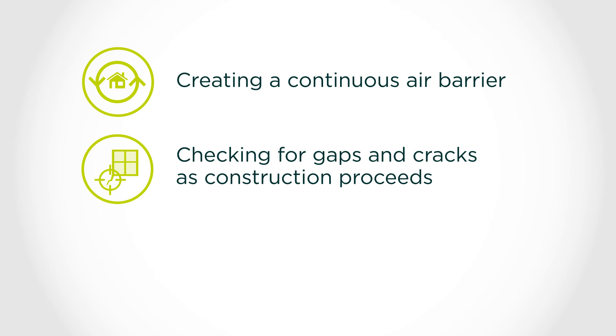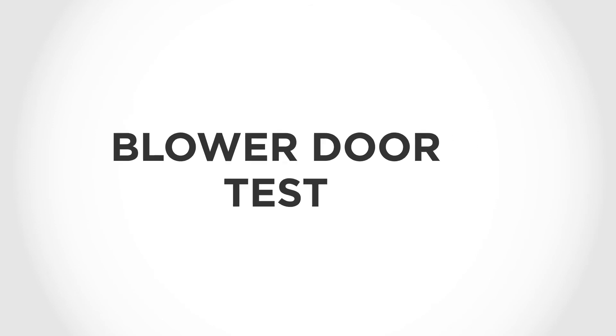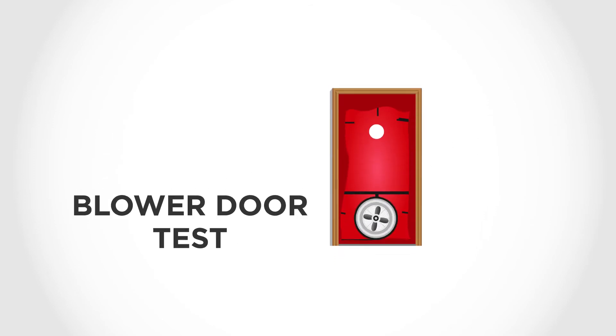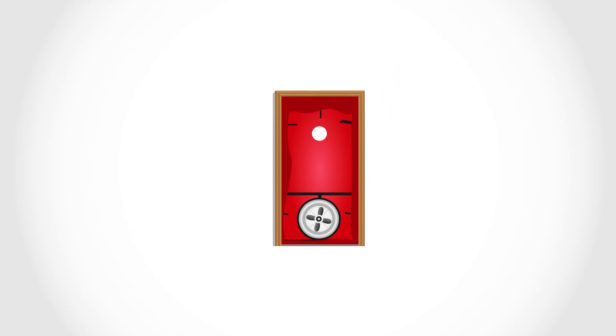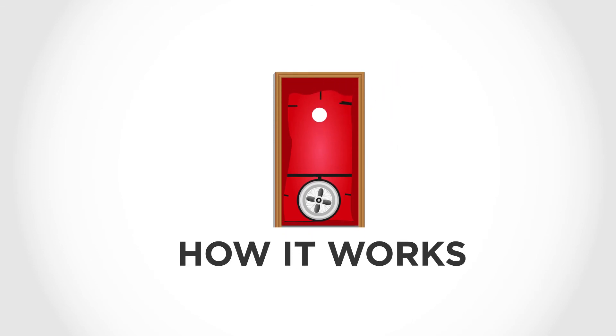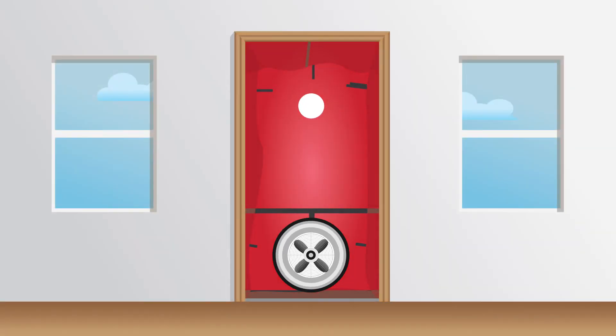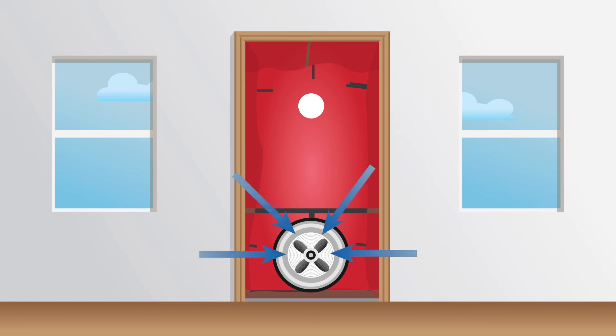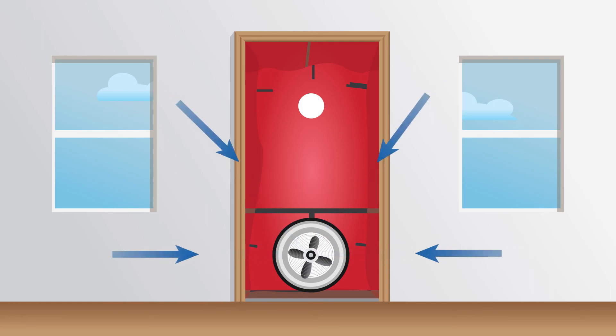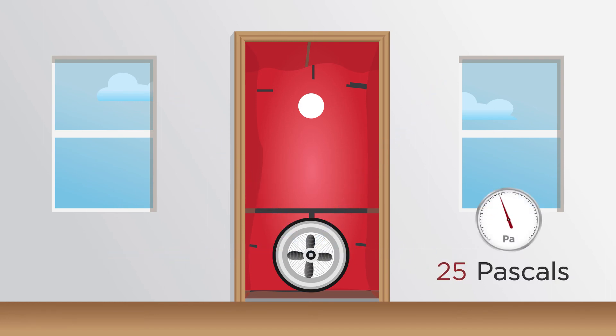Now let's discuss the blower door test. Once construction is complete, including all final envelope penetrations, it is time for the blower door test. Projects must use a blower door test to prove air tightness during final inspections. This is how it works. A powerful fan is set in a doorway and creates a pressure difference between the inside and the outside of the house, usually by depressurizing the house to 50 pascals.